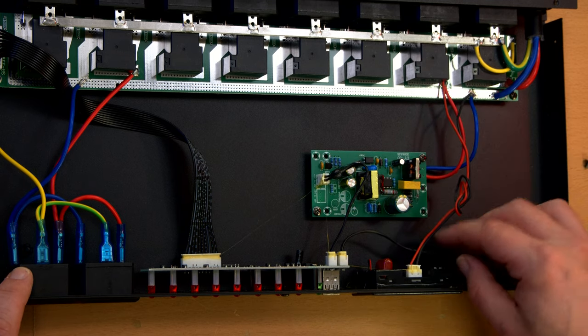keeping my hands well clear of the inside of this thing. There are better ways to test this, of course, but they're less fun ways. So let me put this on the neutral or what should be the neutral because it's unswitched and just touch that to the ground. All right, good. At least we're not seeing any voltage there. So apparently then if I monitor between the live and the neutral bus, we get 119 volts. That is good.